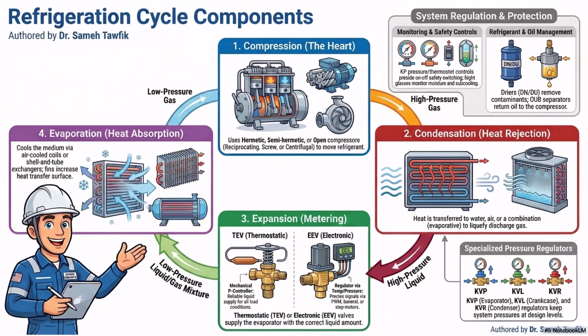Its sole job is to drop the pressure dramatically and ensure the evaporator gets the exact correct amount of liquid under all possible load conditions. No more, no less. It's a great analogy, but you have to understand, the stakes for this bouncer are incredibly high. Oh, so? Well, the TEV has to guarantee that the refrigerant evaporates entirely before it leaves the chilling coils. It has to create a specific condition known as superheat. Superheat. Okay, what does that mean? Superheat means the vapor leaving the evaporator has been heated slightly above its boiling point. Why does the TEV care so much about this? Because it ensures absolutely zero liquid makes it back to the compressor.